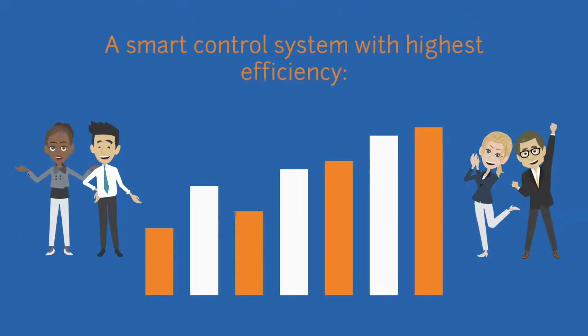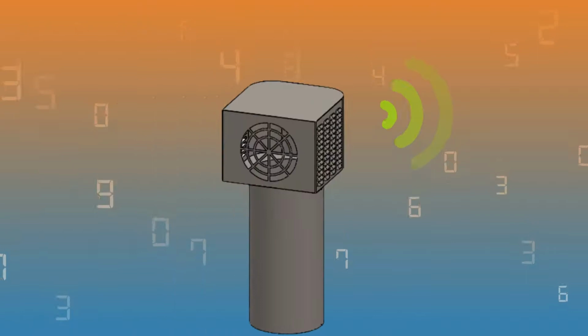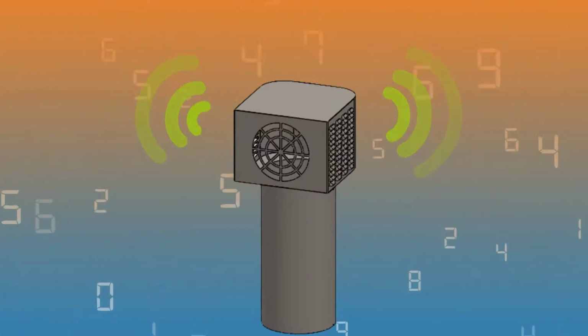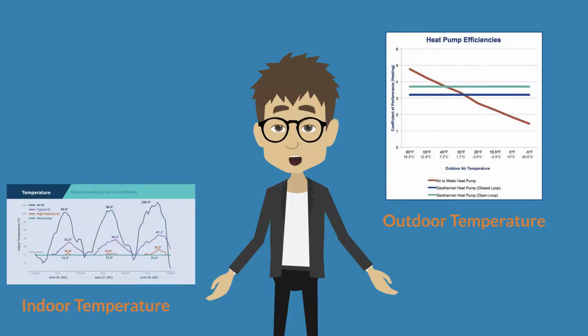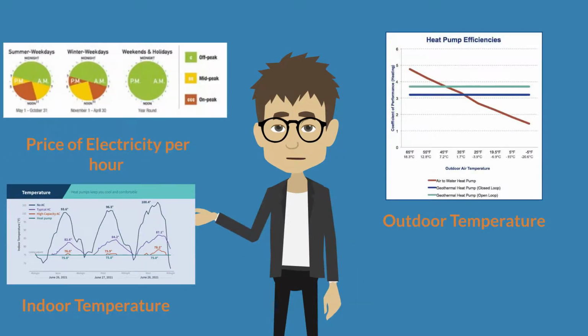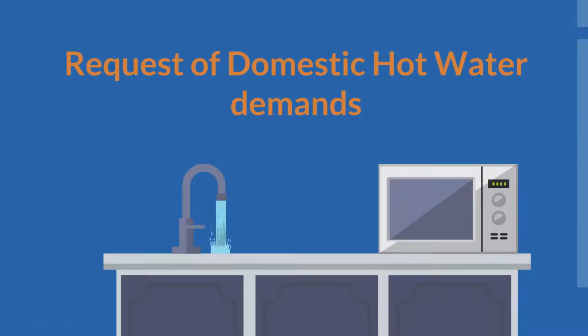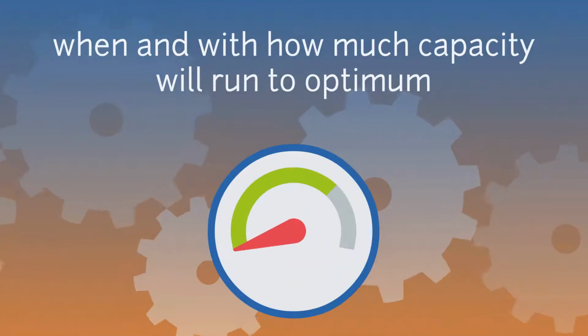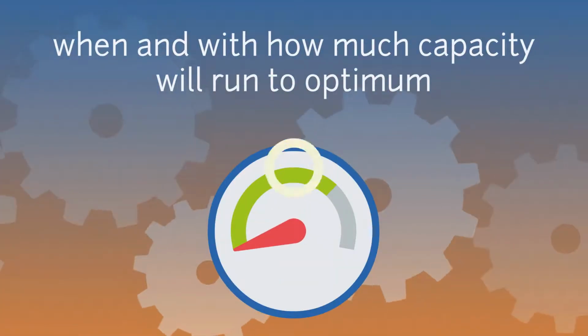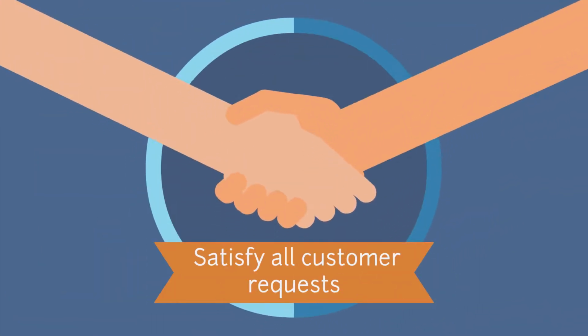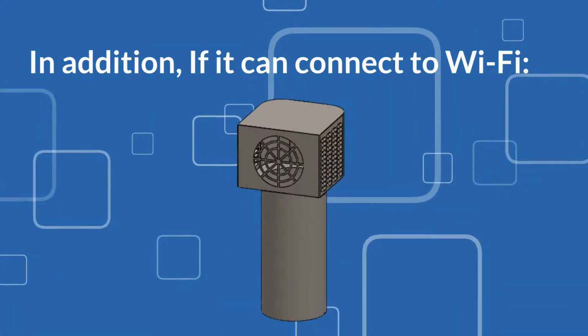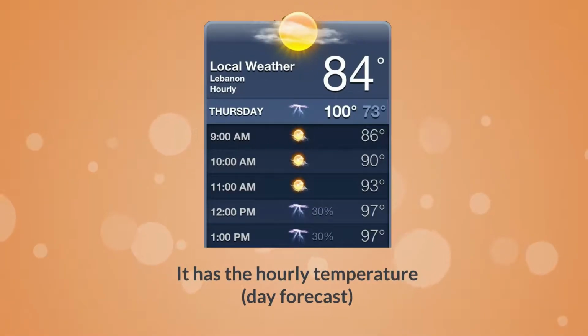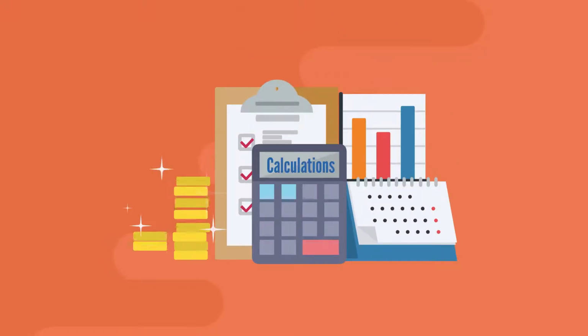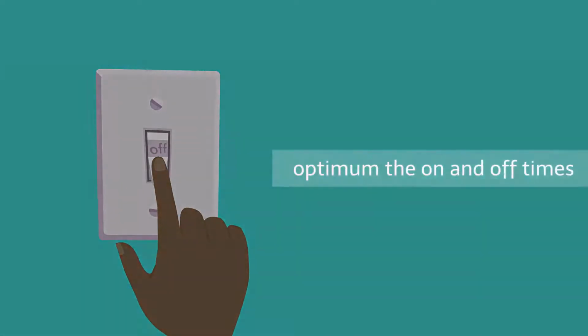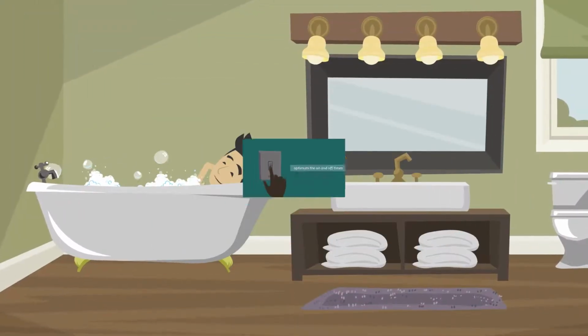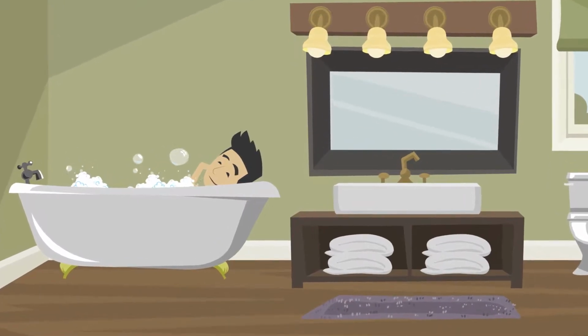B. A smart control system with highest efficiency. This thermodynamic cycle makes this appliance very smart, especially when it connects to Wi-Fi. 1. It knows the indoor temperature, outdoor temperature, price of electricity per hour, and the domestic hot water demands, so the appliance can determine when and with how much capacity it will run to optimize and satisfy all customer requests. 2. In addition, if it can connect to Wi-Fi, it has the hourly temperature day forecast, so it can use it in its calculations and optimize the on and off times, plus recommend the economic times to the customer for using domestic hot water, taking a shower.